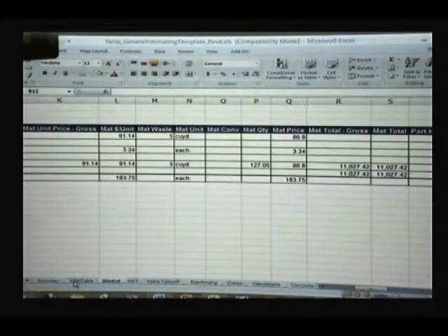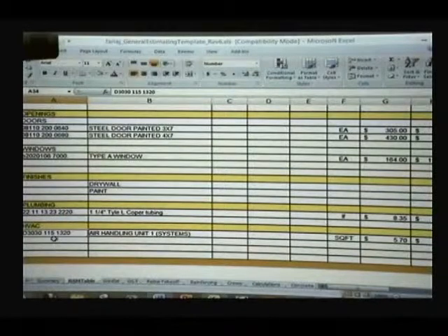So now in our table, we have a cost for the ducts. So the cost for the ducts is here. We have rectangular metal ducts. We'll use galvanized steel under 2,000 pounds. The cost is 47 cents for materials and 4.68 installation, right?